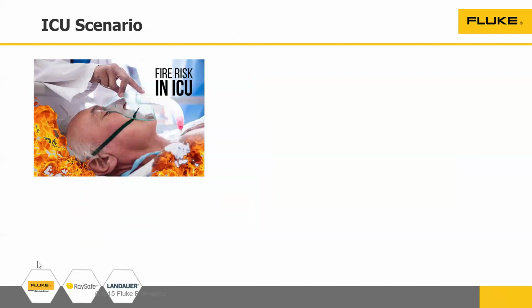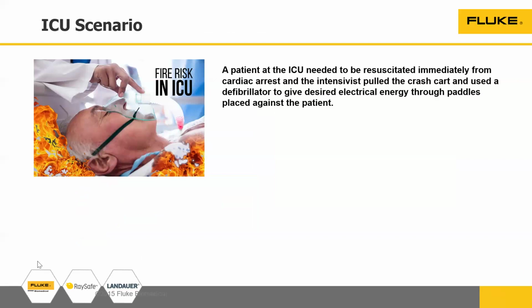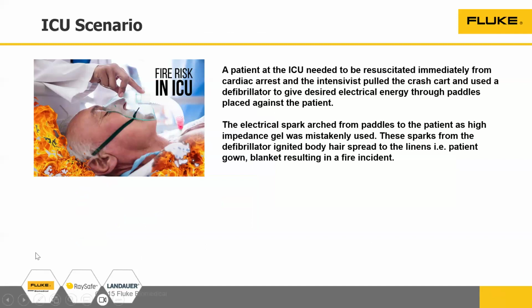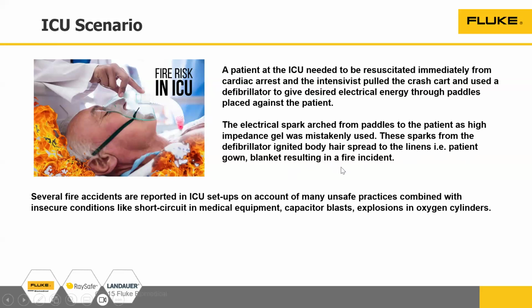So I'll take you to a scenario wherein a simple fire risk from a defibrillator can be triggered. A patient at the ICU needed to be resuscitated for a cardiac arrest, and an intensivist pulled in the crash cart and used a defibrillator to give the energy. The unfortunate part is that during the electrical spark arc from the paddle, high impedance gel was mistakenly used on the patient. These sparks from the defibrillator ignited body hair, which spread to the linens, that is the patient gown and blanket, resulting in a fire.